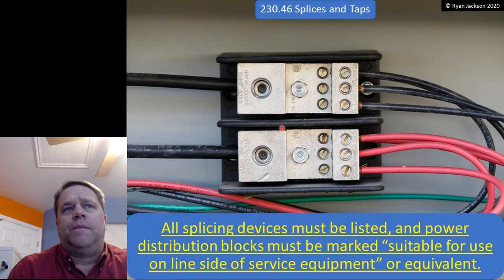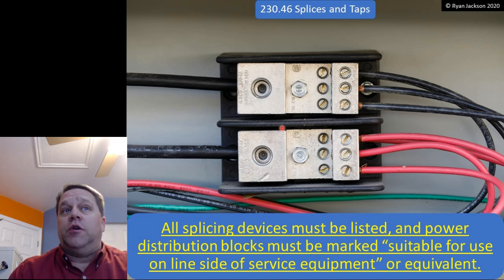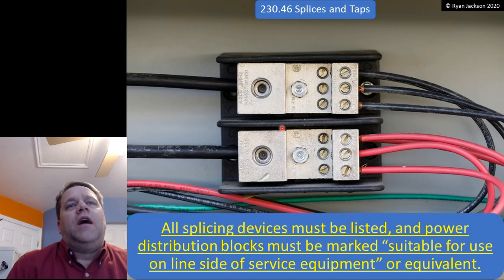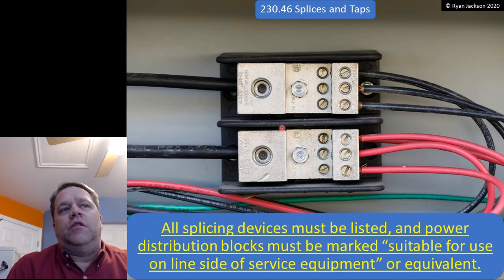Here's what changed. All splicing devices for service conductors now have to be listed, and power distribution blocks, like the one in the photograph, have to be marked suitable for use on the line side of service equipment or similar.